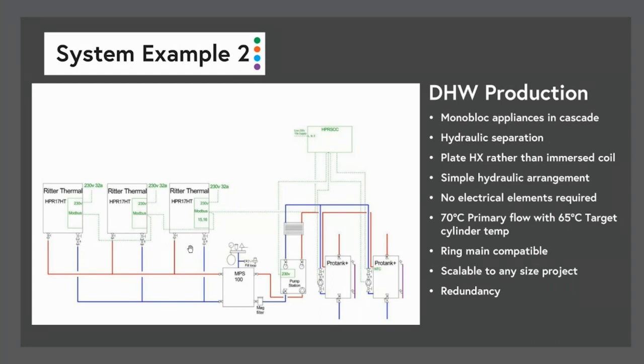The other thing to notice here, no electrical elements. So we wouldn't even put an electric element in this. And a lot of people would say, wow, how are you going to get away with that? Well, the idea is you have multiple heat sources up front. So you have your redundancy built into the primary side. And we're producing high enough temperatures that we don't need elements for boosting on the secondary side. And if we do have a problem, we've got redundancy built into the system.